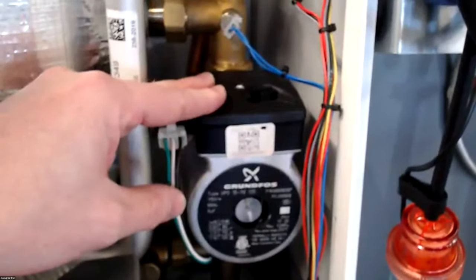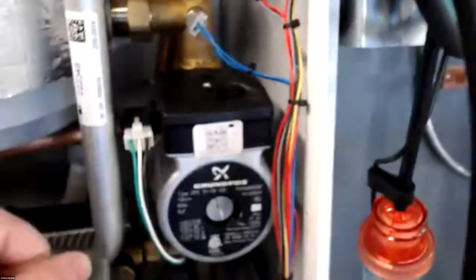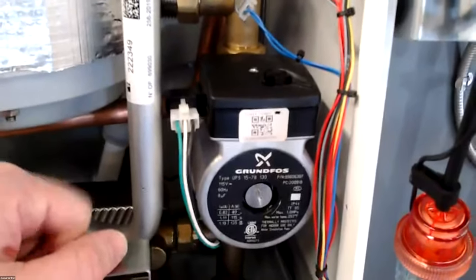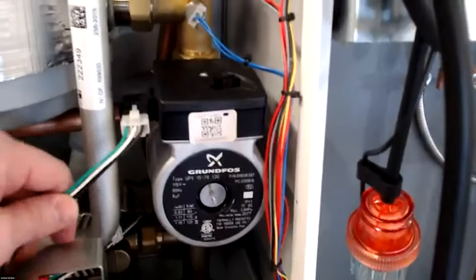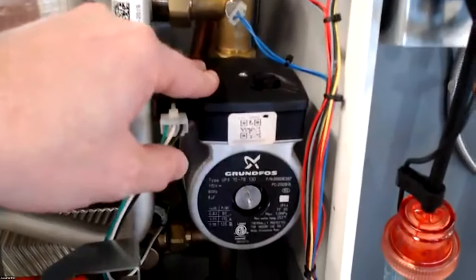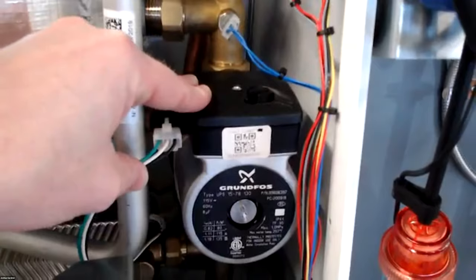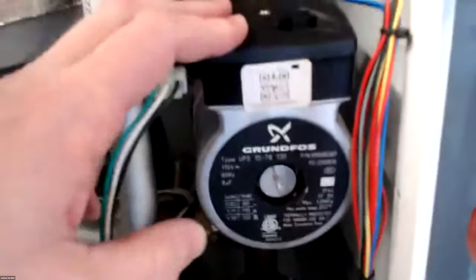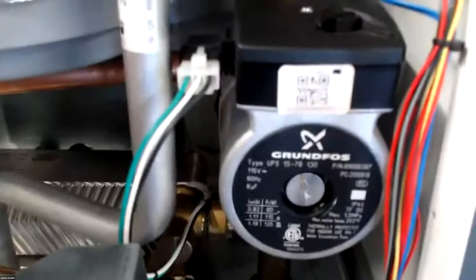Then we have our circulator pump, Grundfos 1578, three speed. You'll get it from the factory, it'll be on three speed. Leave it on there. It's in a no heat call. If you need to get by and change the pump, a 1558 will work. So if you have to throw one in, you can use one of those, but I would definitely come back and put the appropriate 1578 back in here.